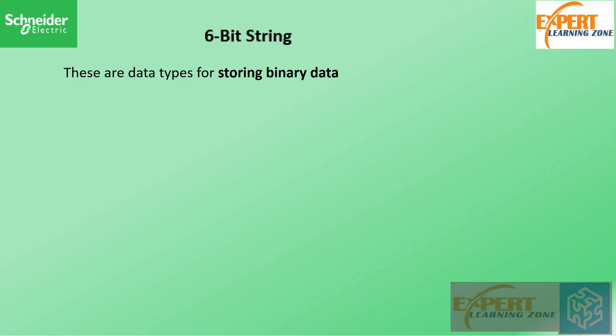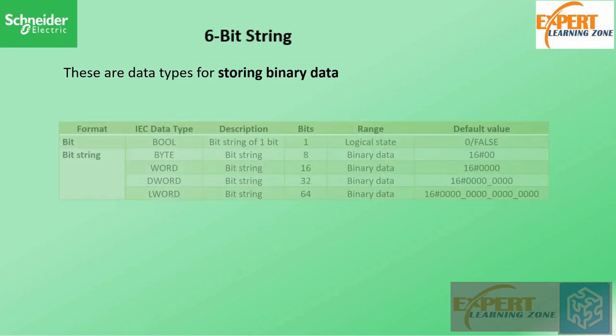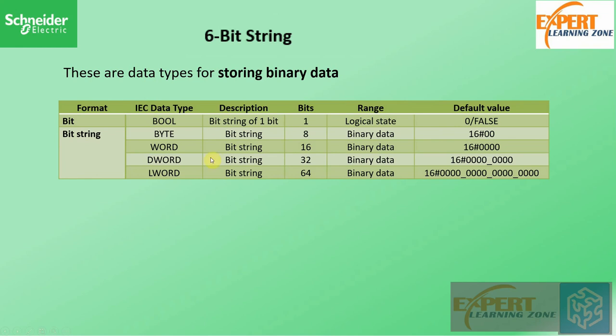Bit strings are data types for storing binary data, generally used to exchange status information with remote devices and for low-level bit manipulation of PLC hardware interfaces. The types are: BIT (BOOL) — 1 bit, with range of logical state true/false; BYTE — 8 bits; WORD — 16 bits; DWORD (double word) — 32 bits; and LWORD (long word) — 64 bits. We mostly use WORD when reading or writing analog values to output memory.